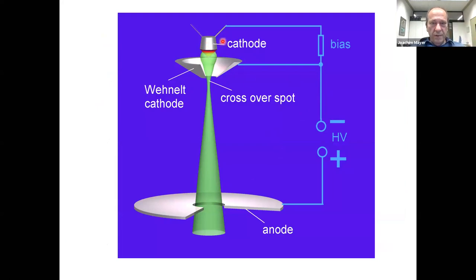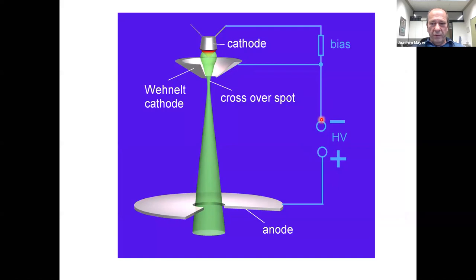Starting at the top with the electron source: we need an electron beam from a cathode. In the simplest case, we heat a tungsten wire to about 2,500 to 3,000 degrees so it emits electrons. We focus the beam with another electrode called the Wehnelt cathode, bringing electrons to a crossover spot, then accelerate them with high voltage — 200,000 or 300,000 volts. This lower electrode is the anode, with a hole of about one millimeter diameter where the electron beam enters the electron-optical column.